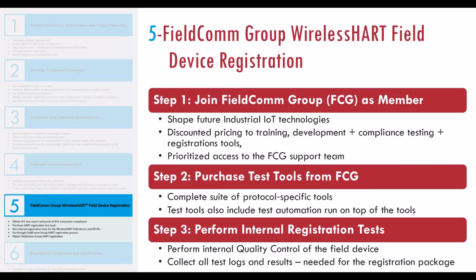You will also purchase the test tools from FieldComm, which include a complete suite of protocol-specific tools that also include test automation in some of these tools. And before submitting the registration package to FieldComm, it's highly recommended that you run some internal registration tests in order to ensure that your device will pass all of the tests that are being run as part of this FieldComm device registration process. So when you're running this internal test, you would collect all the test logs and results because you will need them for your registration package.